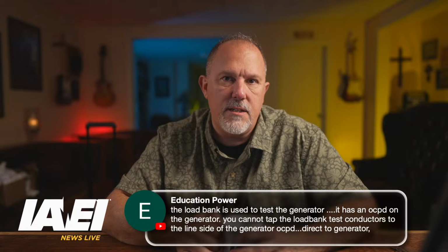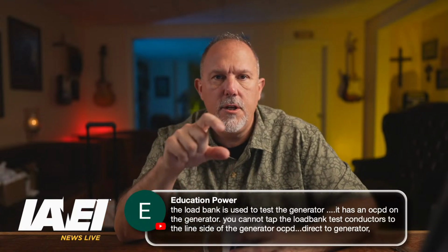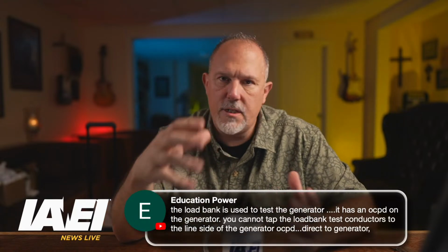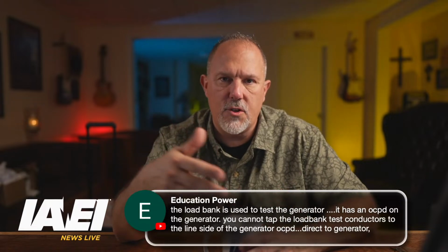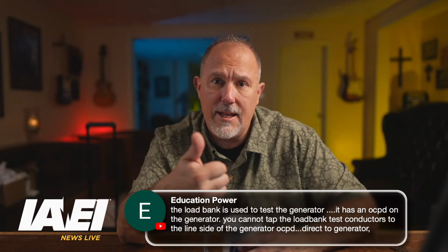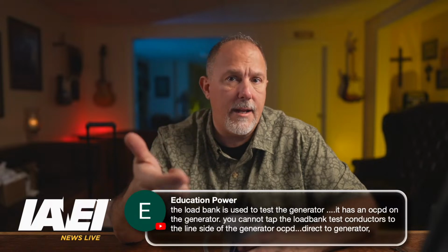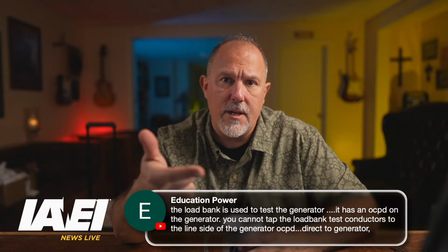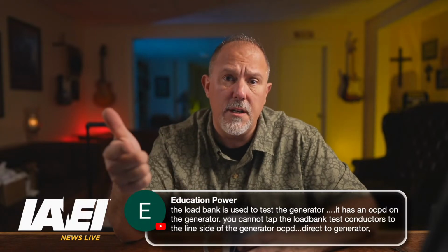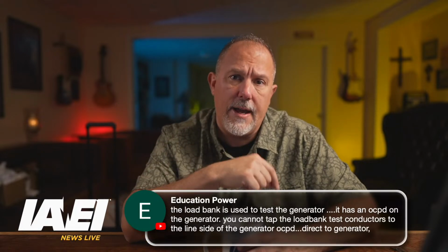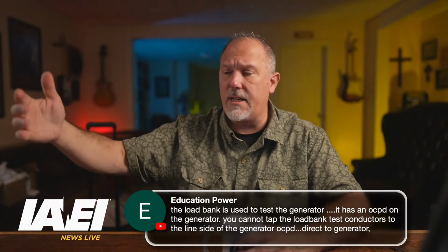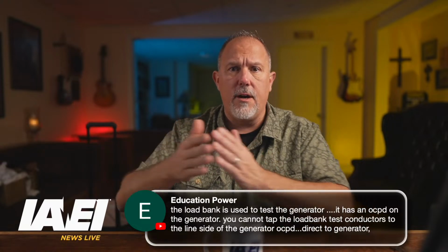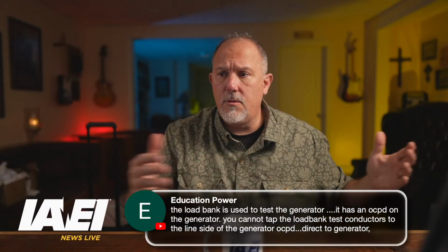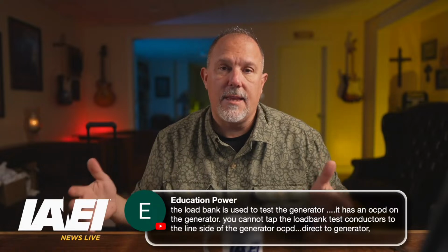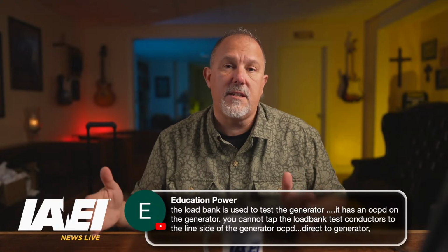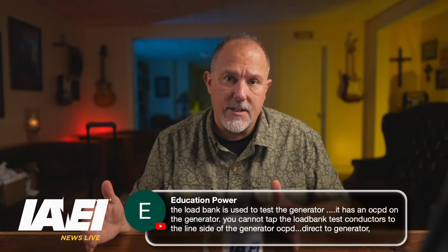So if I was going to put a load bank of resistors or whatever on this generator to run a test, I can't exceed the ampacity of the conductor, and I can't exceed the ampere rating. I would have to make sure that the circuit is adequate for running that load test, because now it's just basically a generator breaker, a conductor, and a load. So that would be a branch circuit under those test scenarios. That's the way I would look at it.